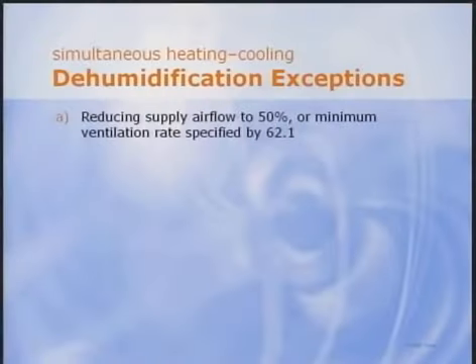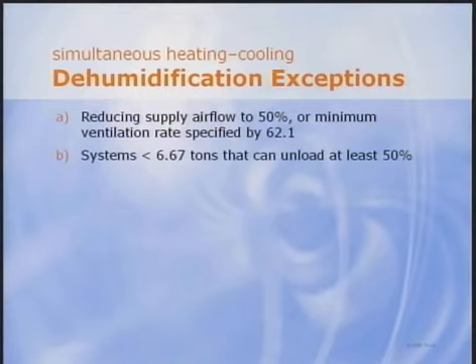The next 2 exceptions allow reheat if there is an individual cooling unit serving the zone. This could be a rooftop, a split system, or even a blower coil with a cooling coil. Exception B allows a unit 6 2/3 tons and able to unload 50% capacity to use reheat at that point. Exception C allows new energy reheat on small units, those 3 1/3 tons or less.